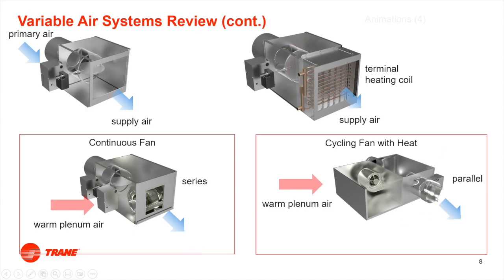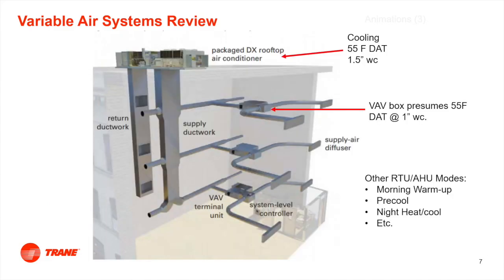With the parallel box, it only runs the fan when it needs heat. So, if we go back to this scenario here, we could simply put that parallel fan box down here when it needs heat, turns on the fan, turns on the heat, and does not have to supply air to the entire system. So, the reason I'm showing you this is you know this now and you didn't know it 2 minutes ago.